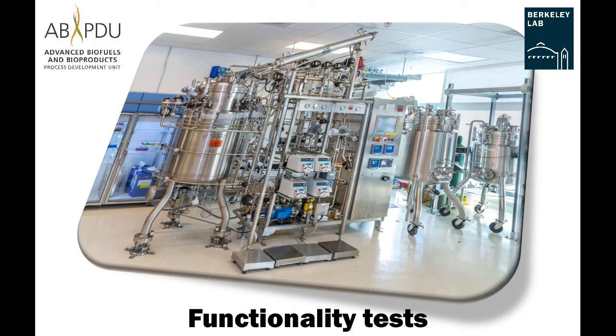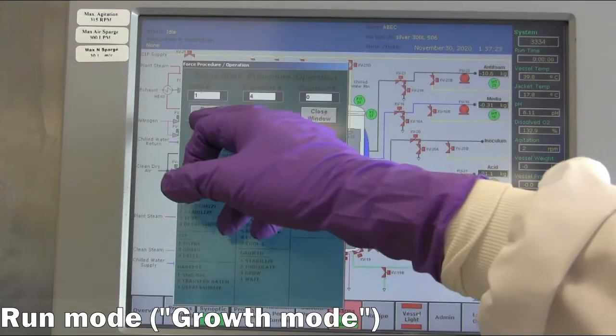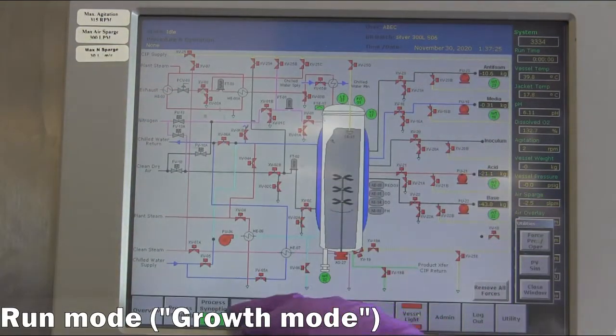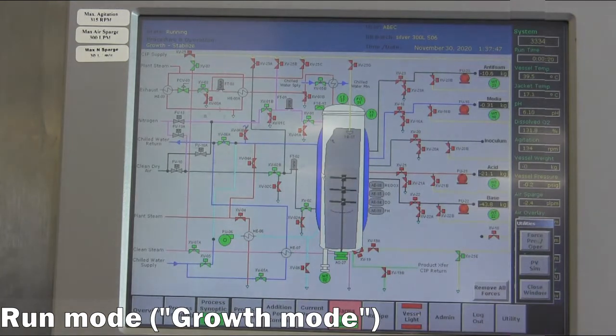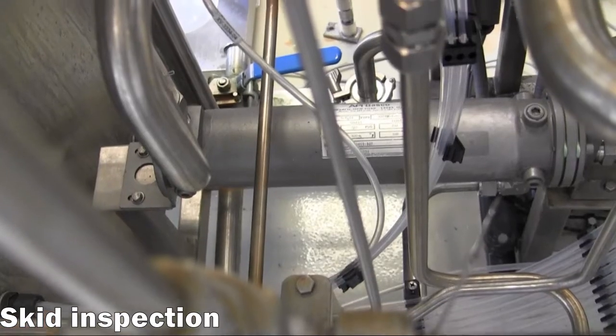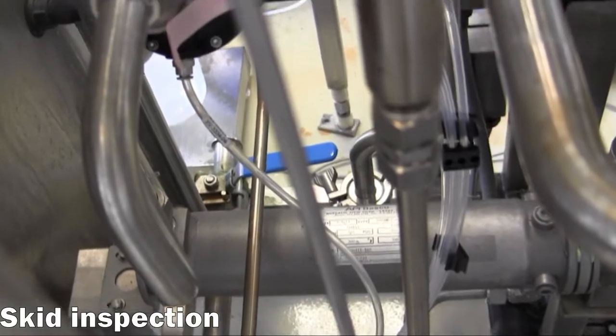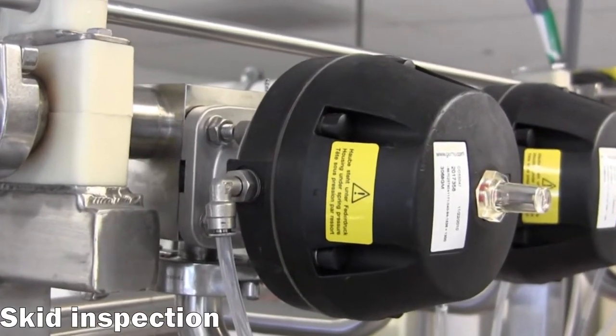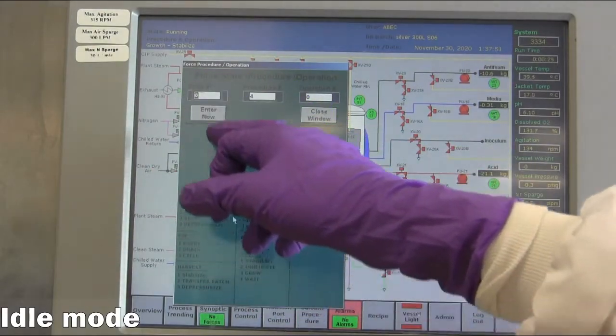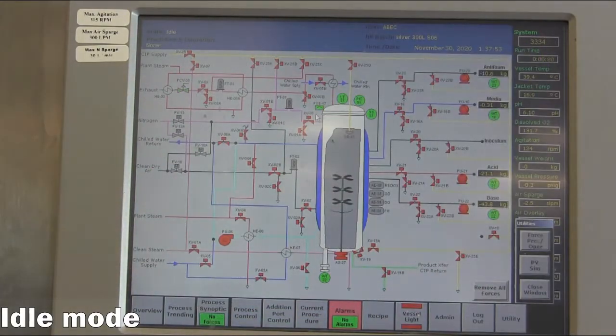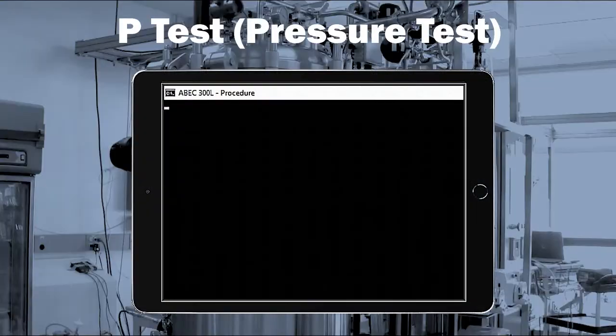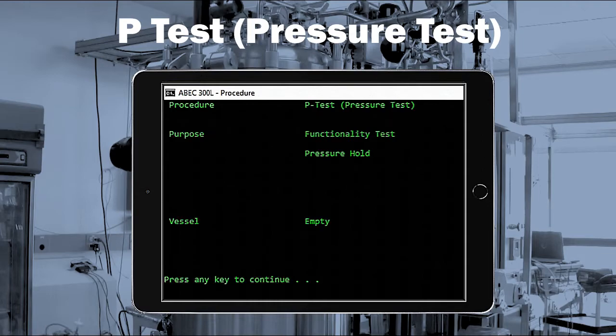Functionality tests. To test the general reactor functions, put the reactor into run mode. After running a couple of minutes and checking for leaks at the heat exchangers and valves, return the reactor to idle mode. Another functionality test that will be performed multiple times during reactor setup is a pressure test, or P-test, to check the ability of the vessel to hold pressure.